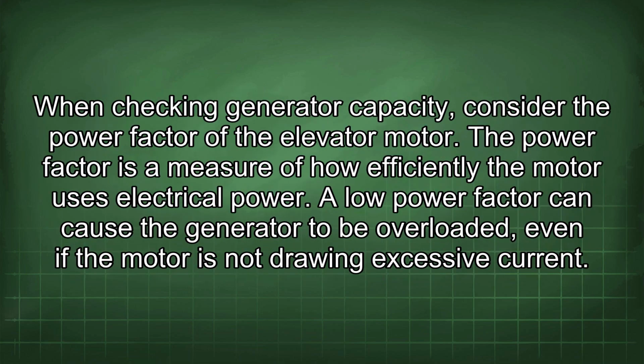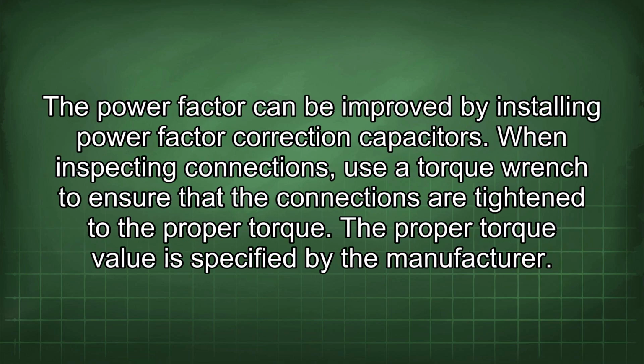When checking generator capacity, consider the power factor of the elevator motor. The power factor is a measure of how efficiently the motor uses electrical power. A low power factor can cause the generator to be overloaded, even if the motor is not drawing excessive current. The power factor can be improved by installing power factor correction capacitors.